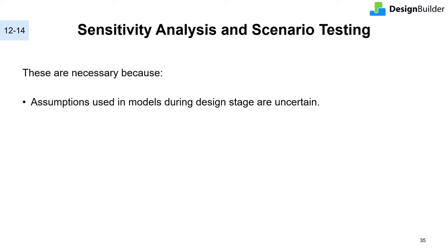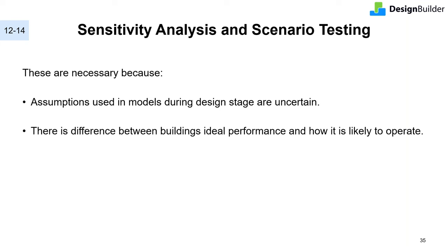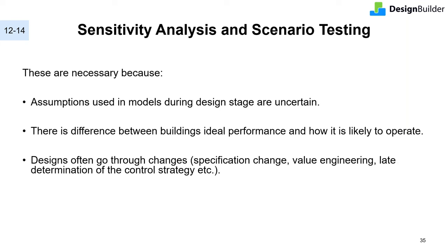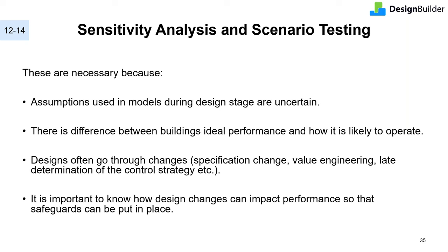Why do we need to look at uncertainty? Models are created using assumptions. As the design evolves, some of these assumptions become more certain, but others — specifically related to operations and occupant behavior — will remain uncertain. This means there will always be a difference between the building's predicted performance and how the building is actually likely to operate. Additionally, designs often go through changes such as value engineering. Using these analyses, we can gain an understanding of how important some of these design changes are, and consequently make stakeholders aware of the need to safeguard energy conservation measures.